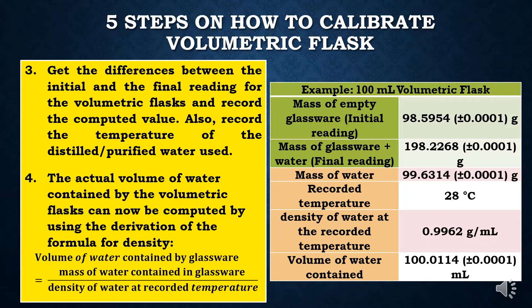Step 4: the actual volume of water contained by the volumetric flask can now be computed using the derivation of the formula for density. Volume is equal to the computed mass or weight of water contained in the glassware divided by the density of water at the specified temperature. Since the recorded temperature of water is 28 degrees Celsius, it has a corresponding density of 0.9962 grams per ml.